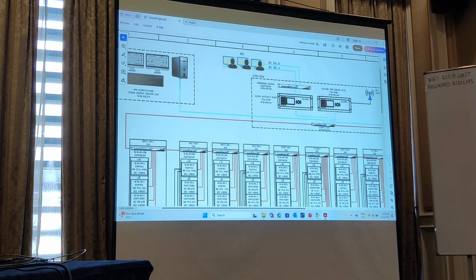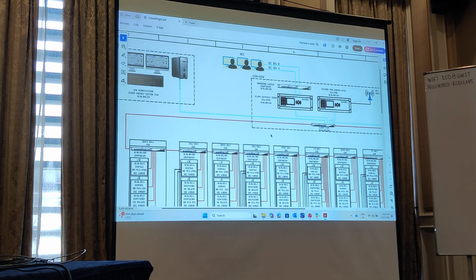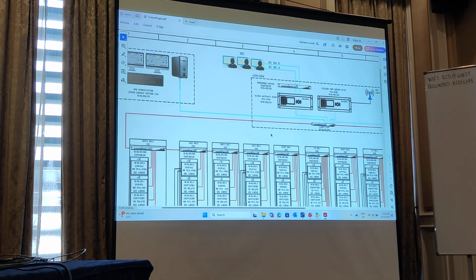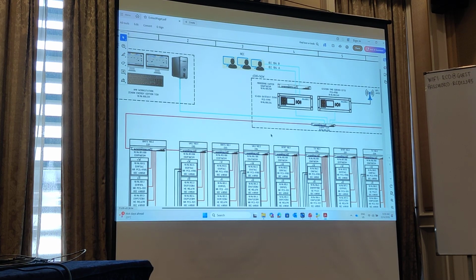So for that communication, the usual thing that we use is Goose, the Goose signals. So from relay going to client, we use MMS signals. So far, Goose signals haven't started being implemented yet. Even until now, the Goose signals haven't started being implemented for client level.